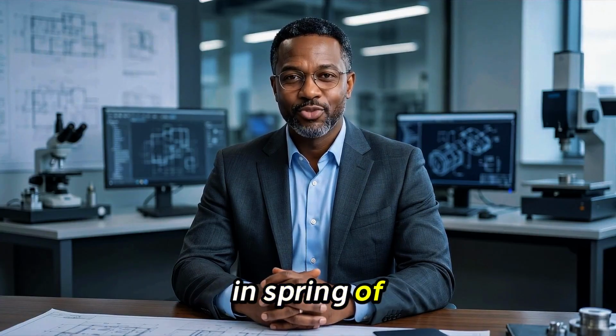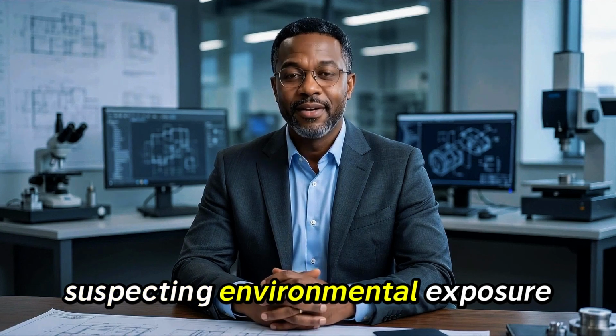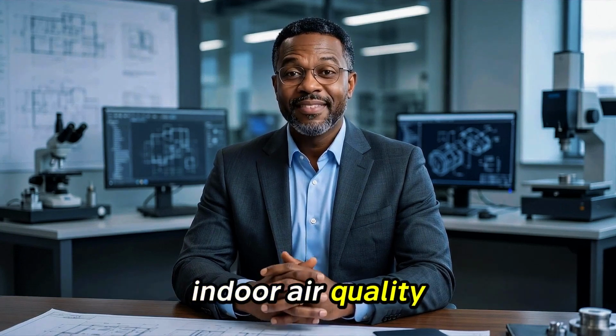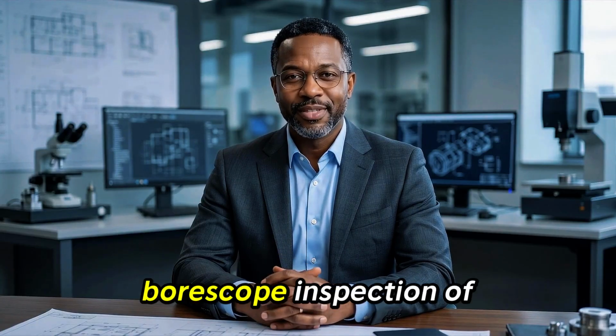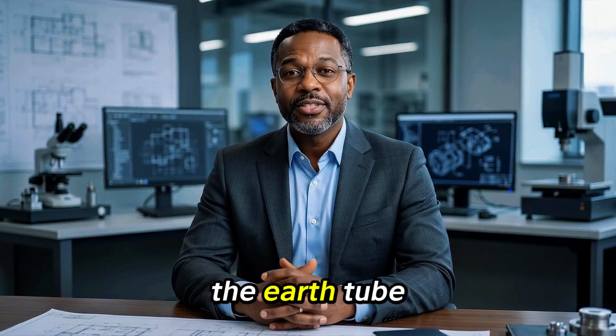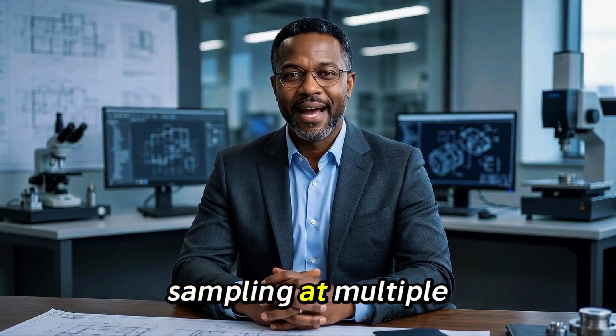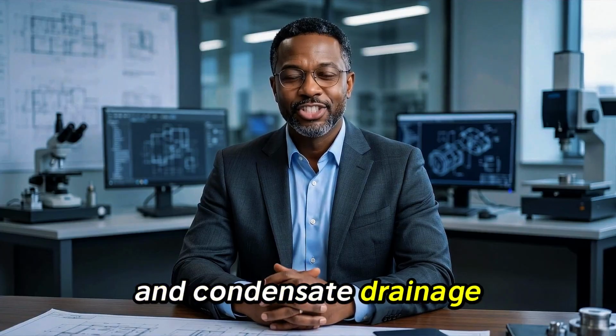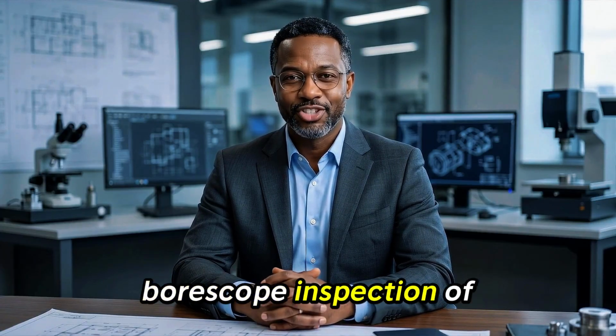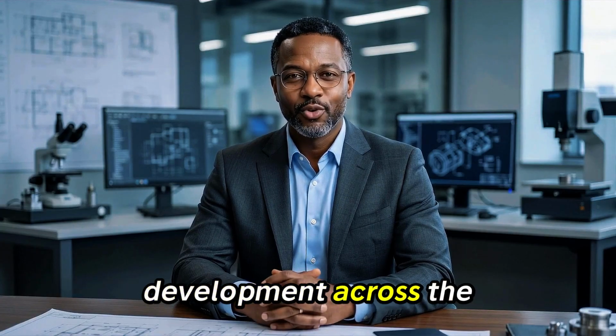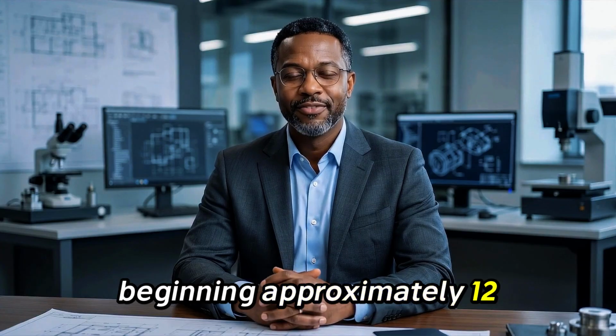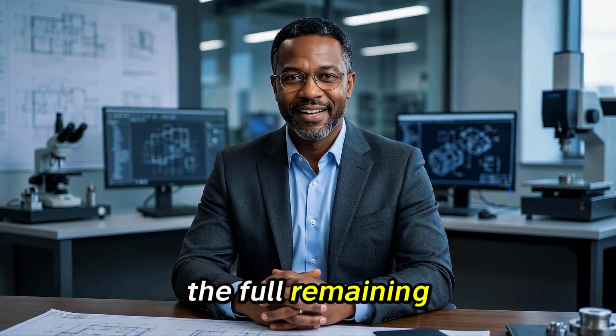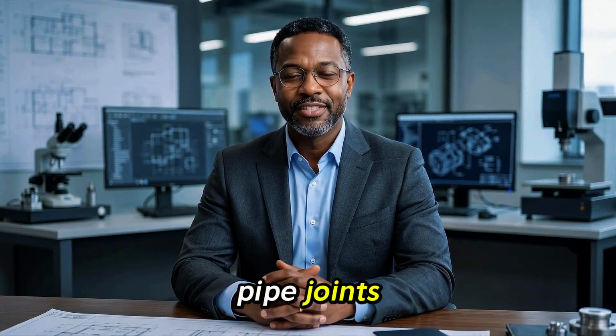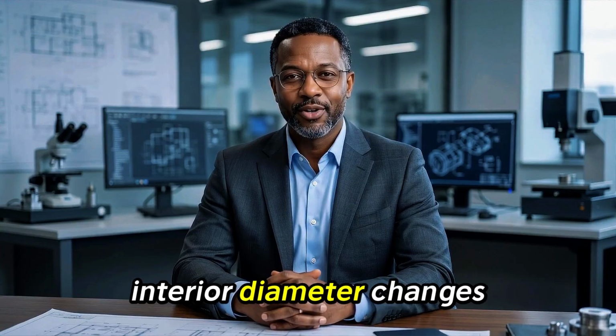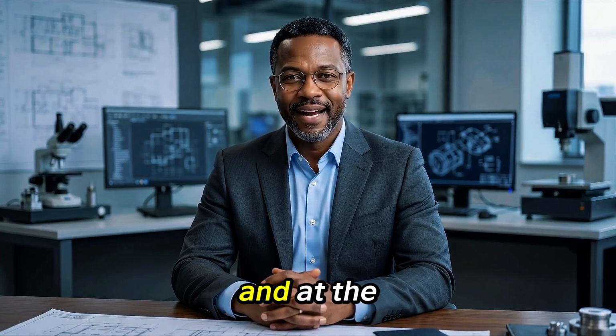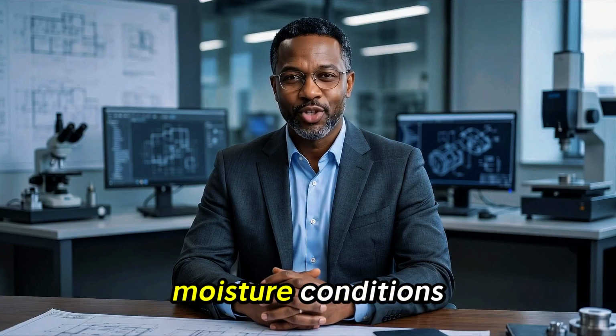They contacted me in spring of 2022 after their family physician, suspecting environmental exposure, recommended a forensic indoor air quality investigation. My investigation protocol included borescope inspection of all 4 earth tubes, air sampling at the earth tube discharge manifold, indoor air quality sampling at multiple locations throughout the home, and condensate drainage assessment at the pipe low points. The borescope inspection of all 4 pipes revealed extensive biofilm development across the interior surfaces, beginning approximately 12 feet from the intake end and continuing through the full remaining length of each pipe. The biofilm was heaviest at the pipe joints, where the HDPE couplings created slight interior diameter changes that accumulated condensate and debris, and at the pipe low points where standing water had established permanent moisture conditions.